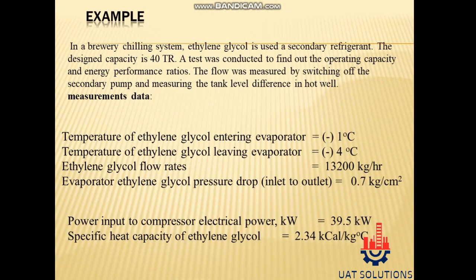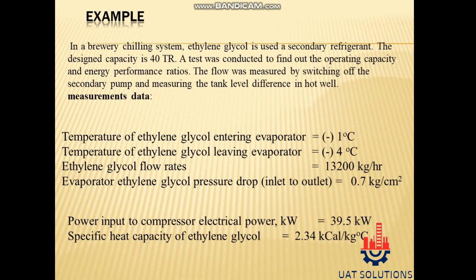Let's practice what we learned via an example. In a brewery chilling system, ethylene glycol is used as a secondary refrigerant. The design capacity is 40 TR. A test was conducted to find out the operating capacity and energy performance ratios. The flow was measured by switching off the secondary pump and measuring the tank level difference in the hot well. Measurements: temperature of ethylene glycol entering evaporator = −1°C; leaving evaporator = −4°C; ethylene glycol flow rate = 13,200 kg per hour; evaporator pressure drop (inlet to outlet) = 0.7 kg/cm²; power input to compressor = 39.5 kW; specific heat capacity of ethylene glycol = 2.34 kcal/kg°C.